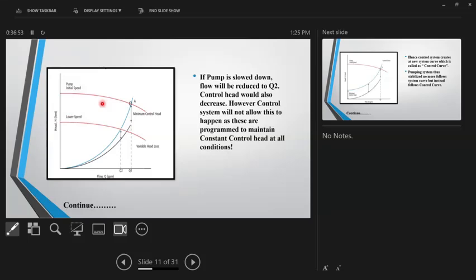Now imagine you are using a VFD. So this was the initial curve in the earlier slide. This was your system pressure. This was resolved into variable and control. So this was initially at flow Q1, which was your initial condition. This was your variable portion. This is your control head.